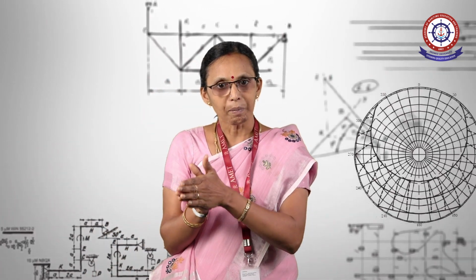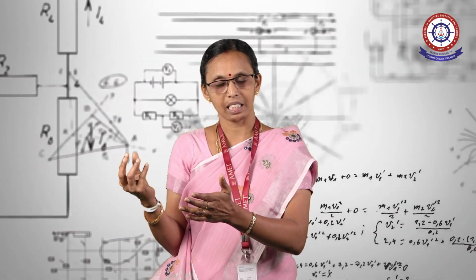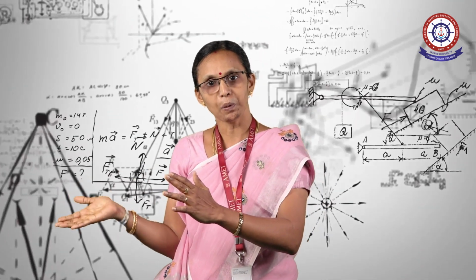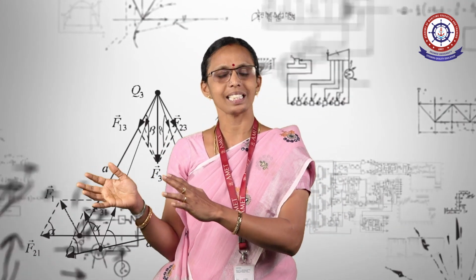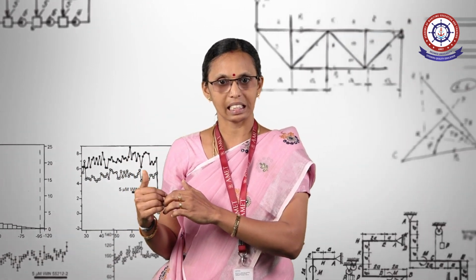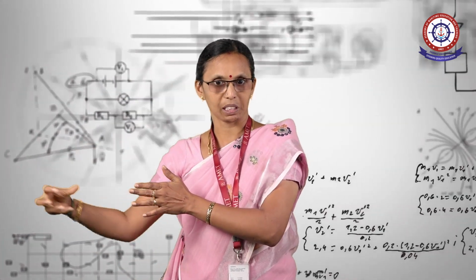From the receiving end station, the power gets transmitted via the secondary transmission system to what we call a secondary substation. There, the 66 kV gets stepped down to either 33 kV or 11 kV. And from there the distribution starts.